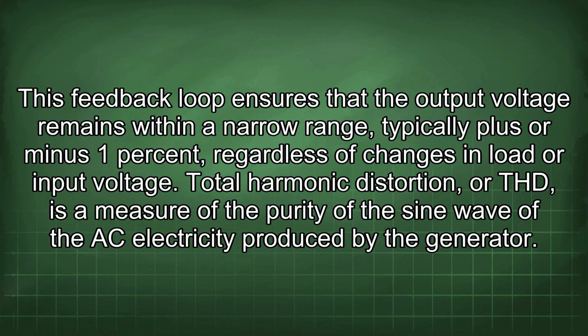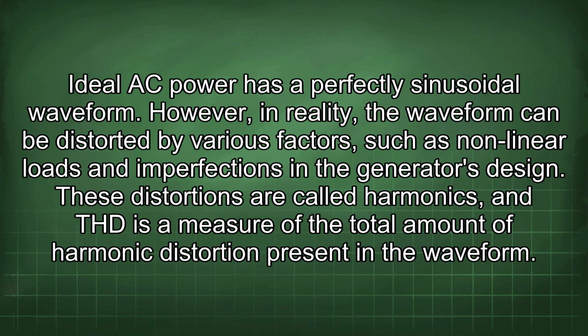Total harmonic distortion, or THD, is a measure of the purity of the sine wave of the AC electricity produced by the generator. Ideal AC power has a perfectly sinusoidal waveform. However, in reality, the waveform can be distorted by various factors such as nonlinear loads and imperfections in the generator's design. These distortions are called harmonics, and THD is a measure of the total amount of harmonic distortion present in the waveform.